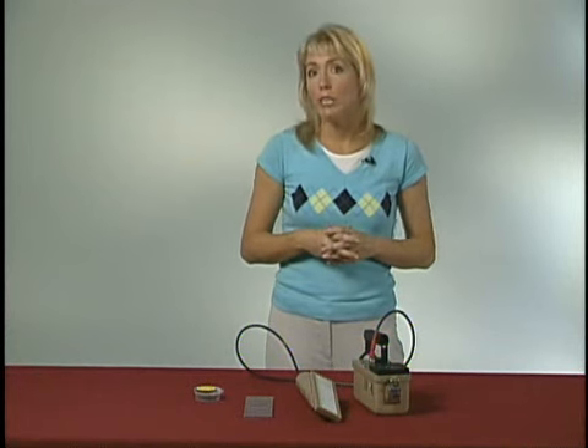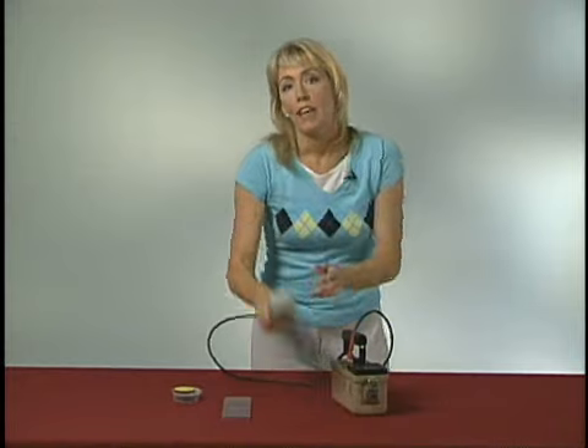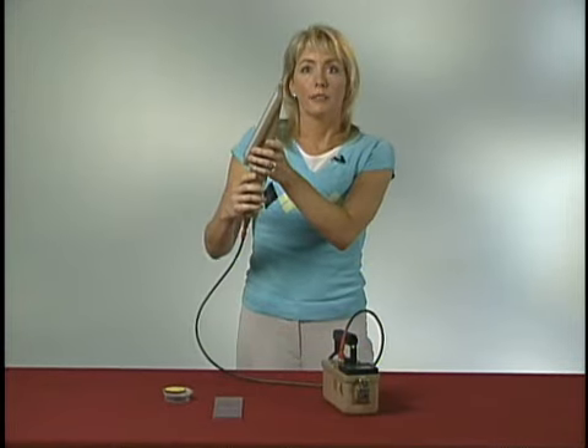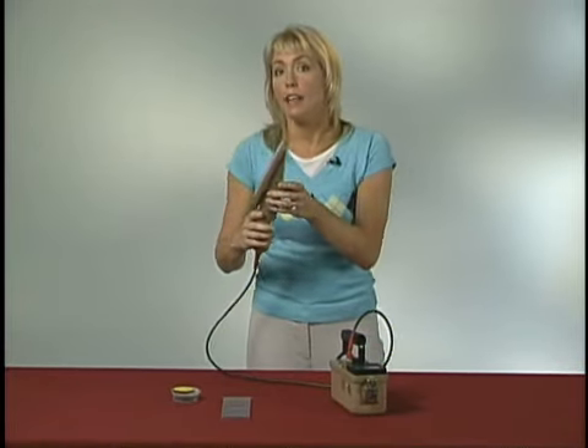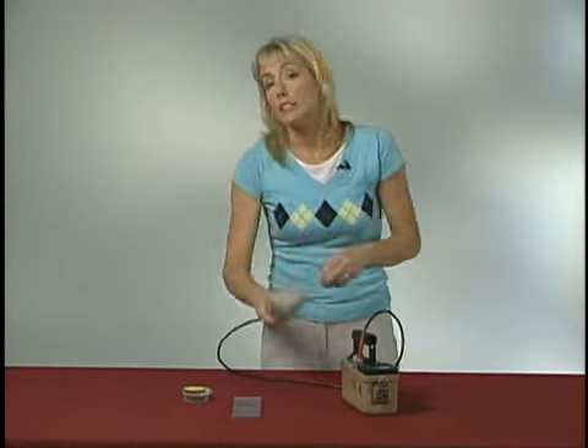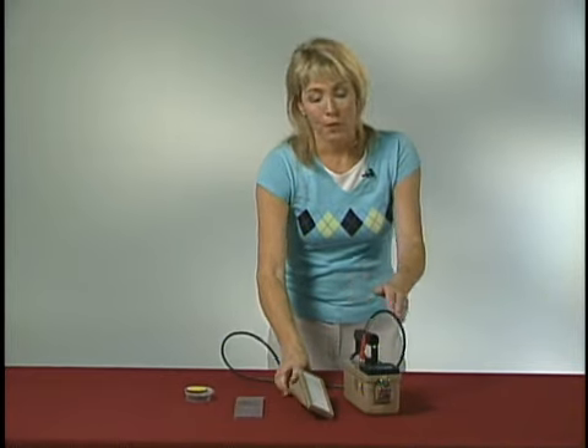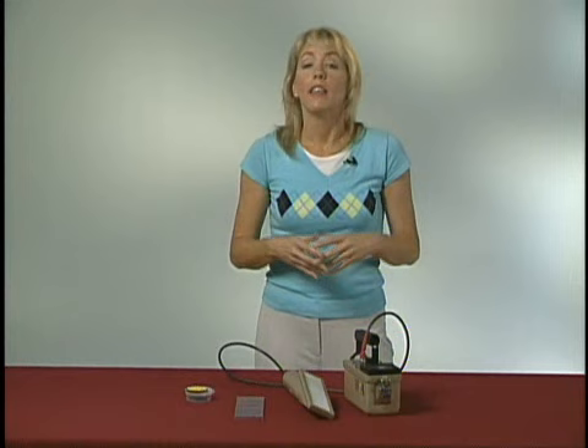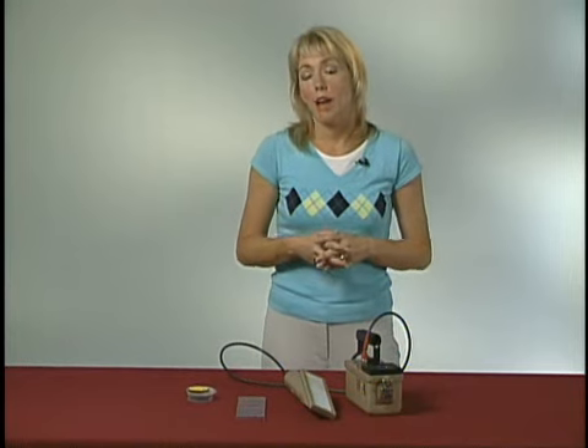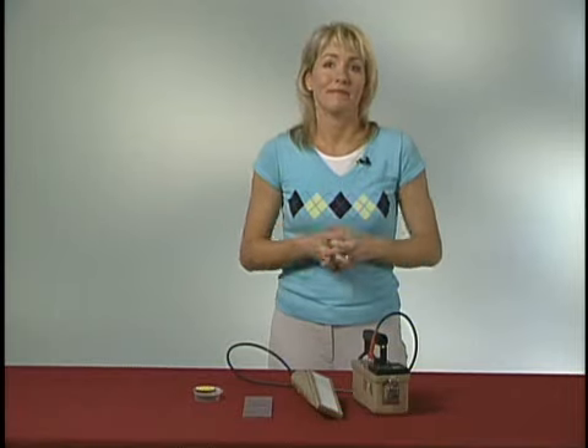Finally, if you're going to use a zinc sulfide alpha scintillator, you need to check for light leaks. With the audio on, point the face of the probe towards a source of light, an open window or an overhead light, for example. If there is a light leak, the meter will register many pulses. Then you need to locate the hole in the window and cover it with paint. In a pinch, a tiny piece of black electrical tape can be used. Once you have determined that the instrument seems to be working properly, you are ready to survey.